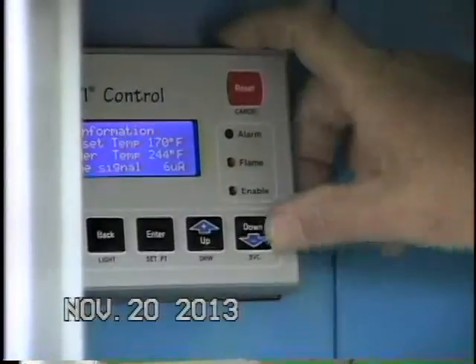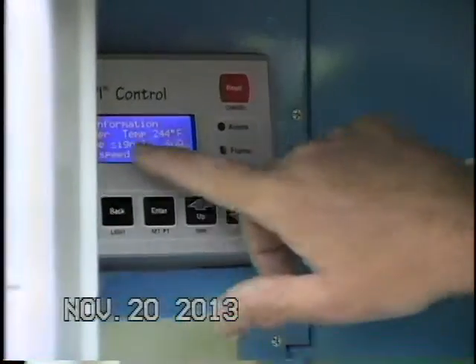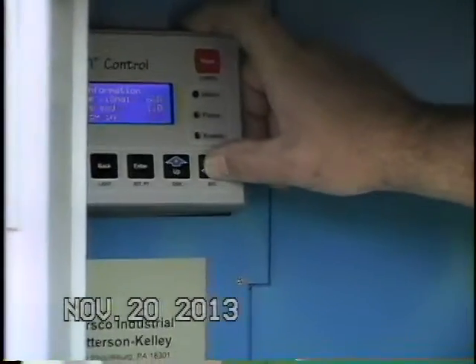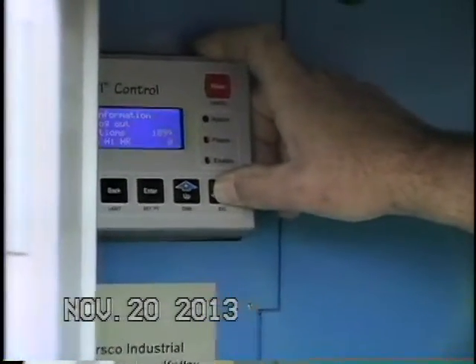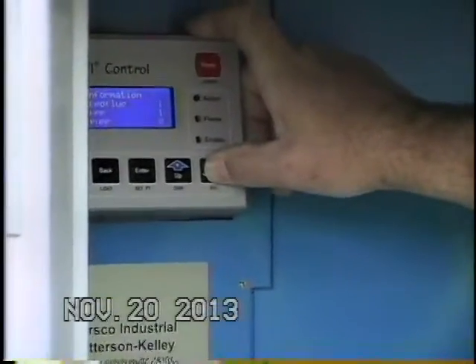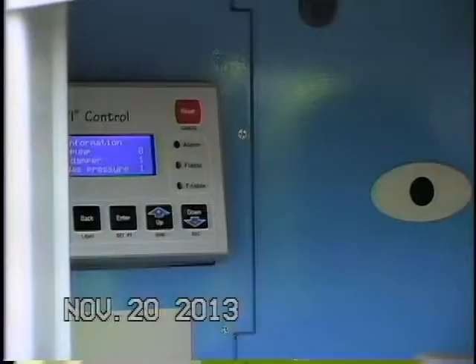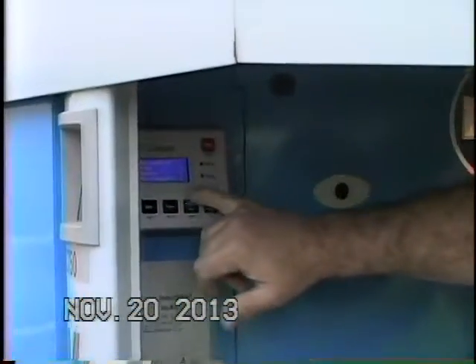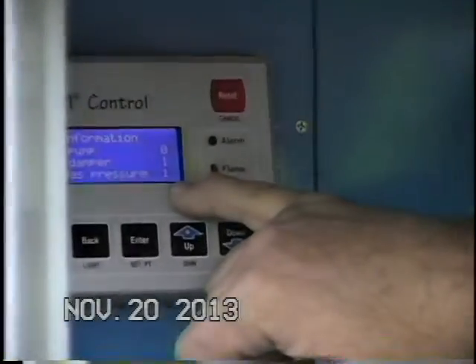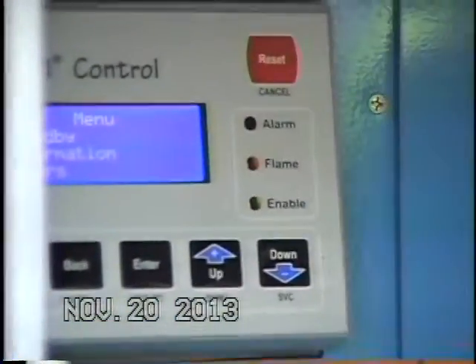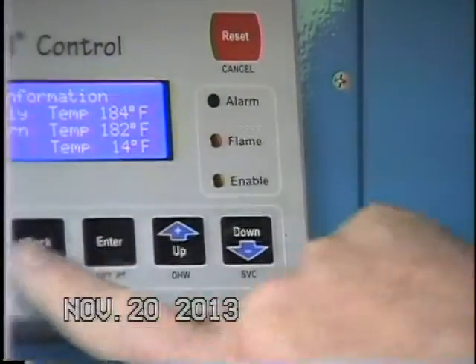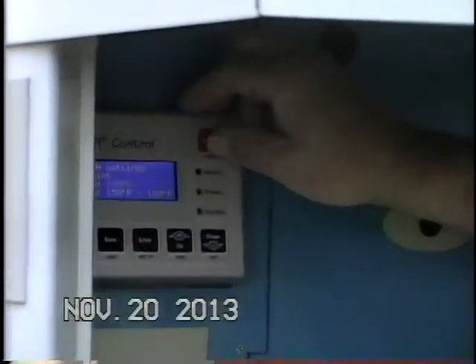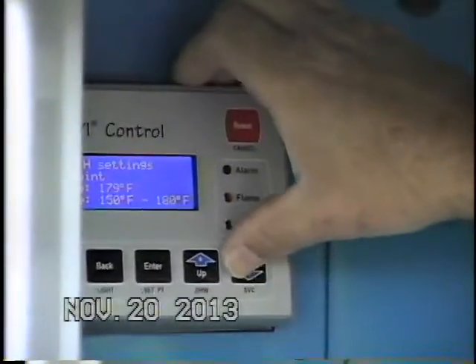We don't have a header sensor on there. Flame signal, and this is 6 microamps. So that you can just kind of go down, and this is all the information you have access to. Okay? Now, as you see the high gas pressure, we have a 1. So if you had an issue, that would say a 0. Okay? So here's your set point. Like if you wanted to change it, it's in the CH settings. You'd hit enter and you just go up and down.